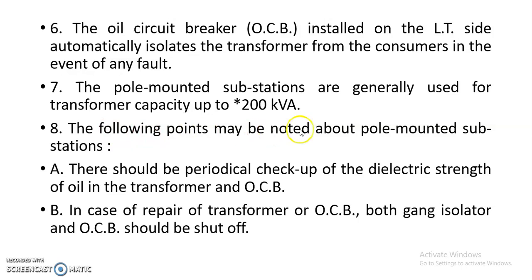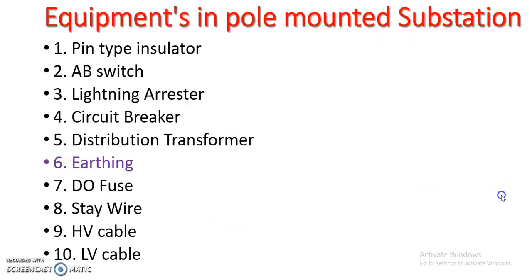The following points may be noted about the pole mounted substation. First, there should be a periodic check of the dielectric strength of the oil in the transformer and the circuit breaker, that is the oil circuit breaker. Second, in case of repair of the transformer or oil circuit breaker, both the gang isolator and OCB should be shut off. It should be open.